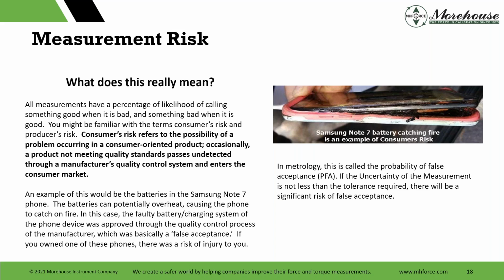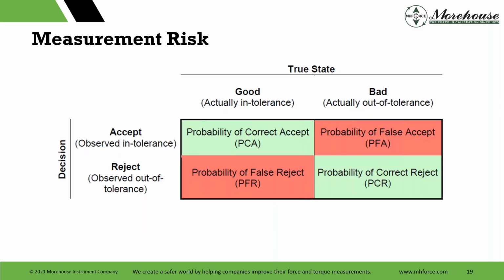In this case, the faulty battery charging system of the phone device was approved through a quality control process of the manufacturer, which is basically a false acceptance. There was a risk to you. If we want to relate this back to metrology, we would call this the probability of false acceptance. If this uncertainty of measurement is not less than the tolerance required, there will be significant risk of false acceptance. And that shows in here.